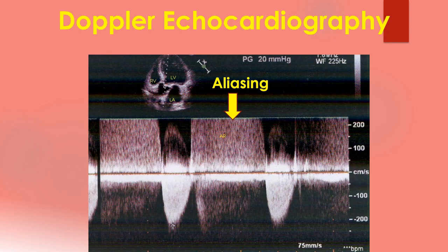In such situations, continuous wave Doppler with a higher velocity range is used. An intermediate option is HPRF or high pulse repetition frequency Doppler. The disadvantage of continuous wave is that it cannot pinpoint the exact location of the high velocity signal, as it is continuously transmitting and receiving the echo signal.